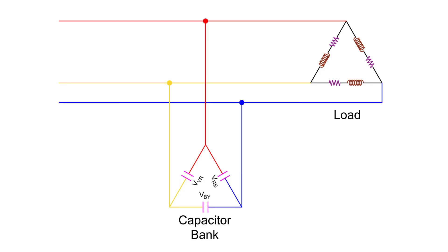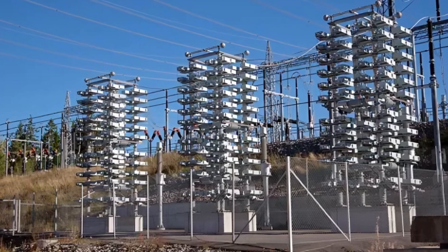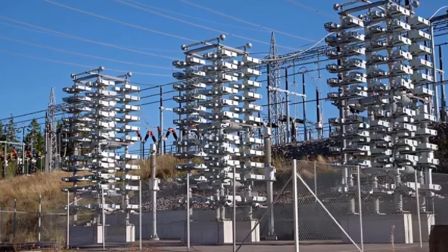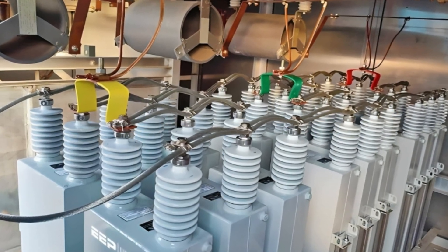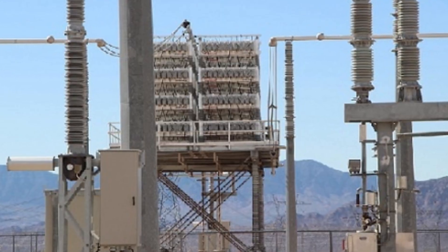So the delta connection is simply more efficient when it comes to power factor correction. It allows each capacitor to operate at full line voltage, maximizes reactive power output, and maintains better system reliability. The ability to continue operating even if one unit fails, and the elimination of the need for a neutral wire—both these features make delta the obvious choice in real-world capacitor bank applications. That's why in most practical systems, be it substations, industrial power factor panels, or utility networks, you'll always find capacitor banks connected in delta.